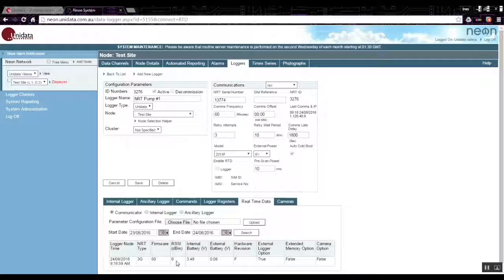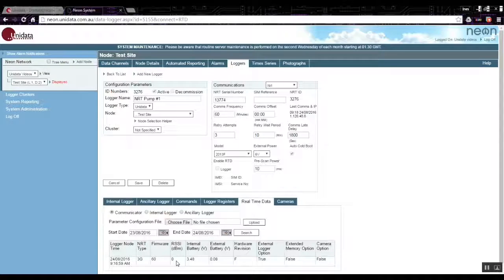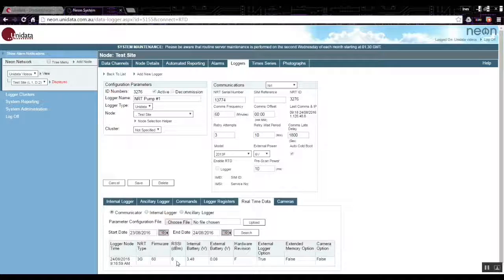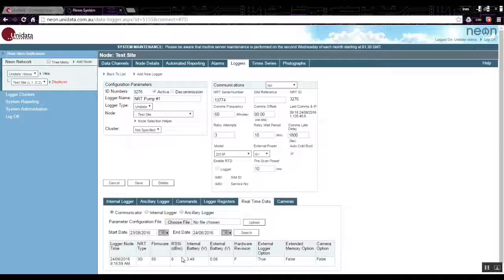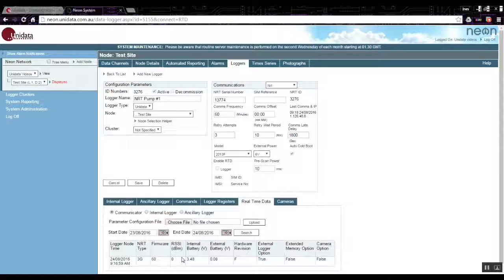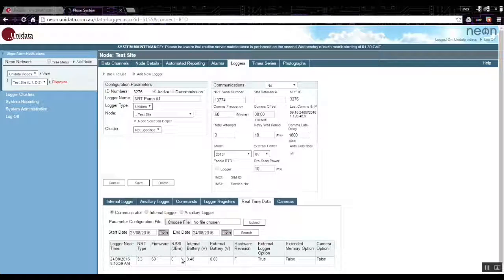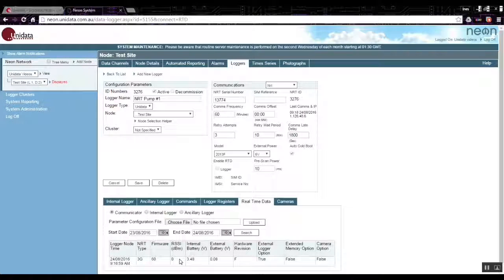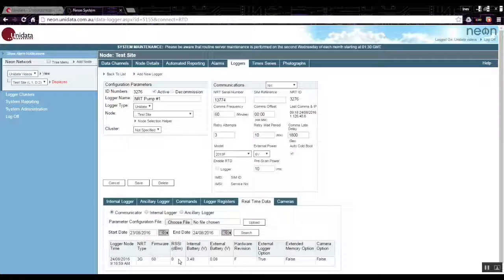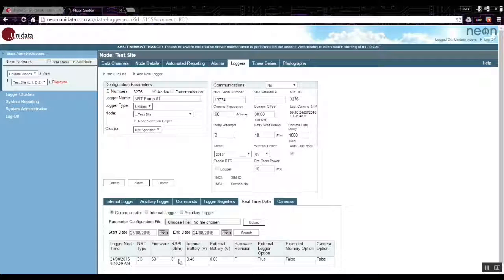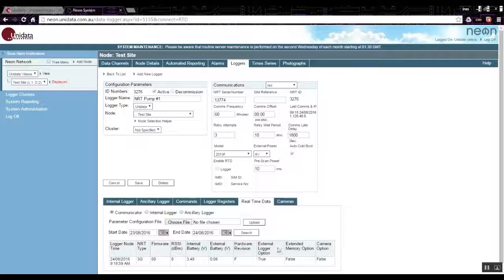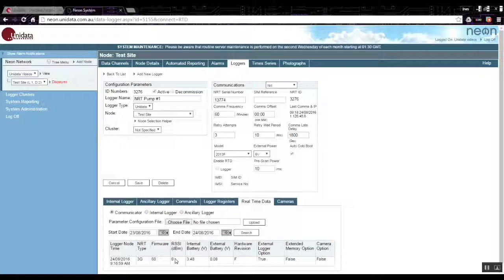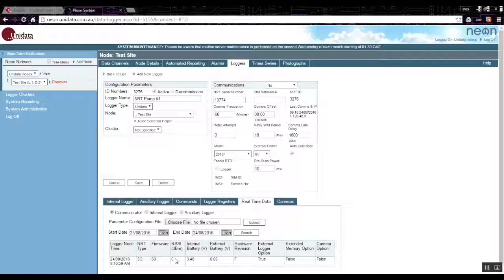Real-time data is just diagnostics information. The useful things here are signal strength RSSI, which is zero in this case but that's typically the case when you first initialize an NRT. Normally RSSI has to be at least minus 85, typically minus 65 perhaps. If you're seeing a number like minus 100 then you have very poor signal strength and you really shouldn't expect your NRT to connect to the server reliably. If that's the case you need to fit an external antenna or relocate the NRT to a better reception site.